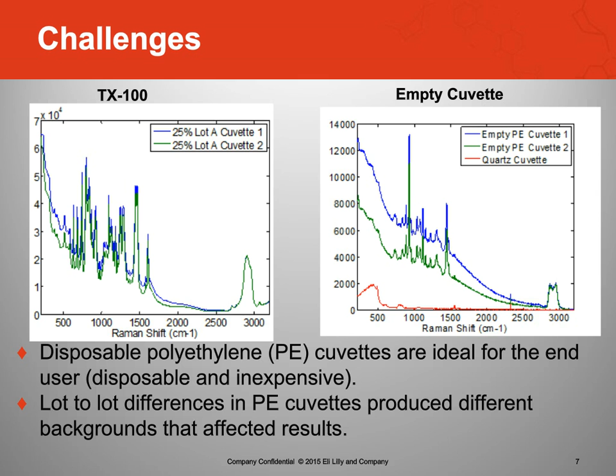The calibration was pretty straightforward. It was over a number of days, and again, these days are listed sequentially, but in most cases it was probably over several weeks. Our target concentration for Triton was 25%. Our target concentration for Tween was 10%. We took an approach similar to what you would expect for ICH guidelines of 80 to 120%. We got a little bit of curvature for Triton, so we narrowed it down from 23 to 27, around the 25, and then did pre-processing, which I mentioned before.